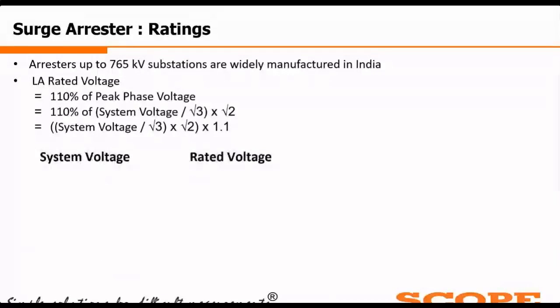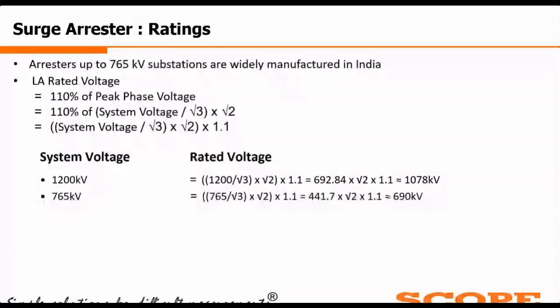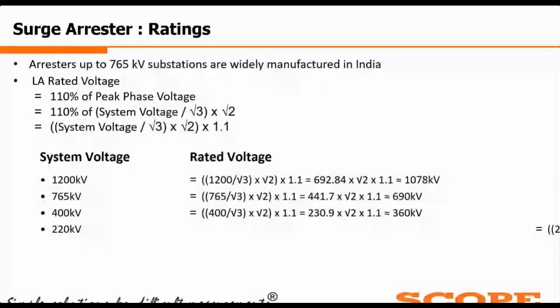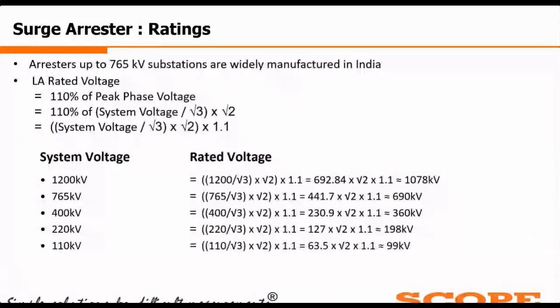So if we see, for a system voltage of 1200 kV, we will get a rated voltage of around 1078 kV. For 765 kV, it will be around 690 kV. For 400 kV, it will be around 360 kV. For 220 kV, it will be around 198 kV. For 110 kV, it will be around 99 kV, and so on.